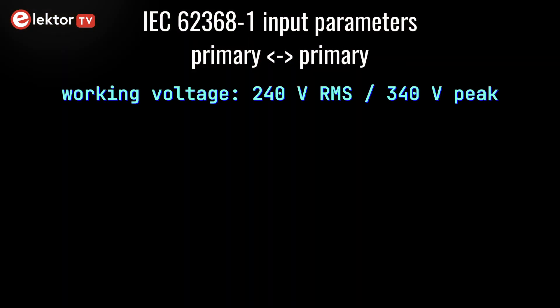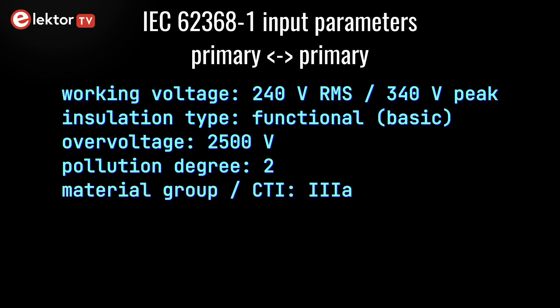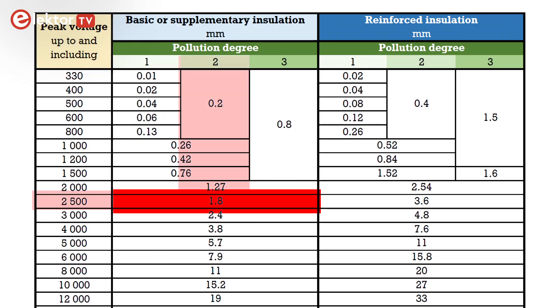For the clearance and creepage distance inside the primary part — for instance around relay switch contacts — we use these values: working voltage 240 volts RMS or 340 volts peak, insulation type functional which means basic, overvoltage 2.5 kilovolts, pollution degree 2.0, material group or CTI 3A, and altitude correction 1. These are the same as before except for the insulation type, which is now functional instead of reinforced, and for which we use the basic insulation values. For clearance we find 1.8 mm, and for creepage 2.5 mm. If the clearance is also set to 2.5 mm like the creepage, then it's good for altitudes up to 4500 meters.